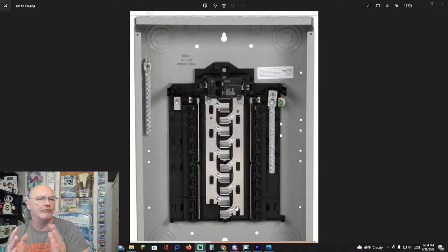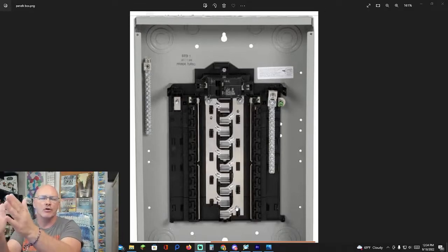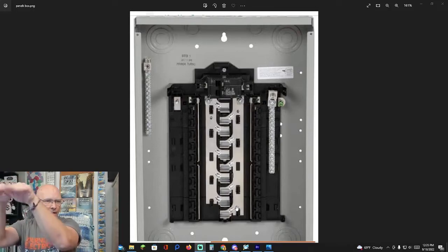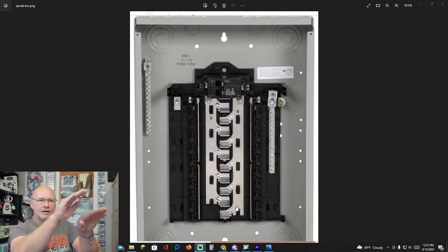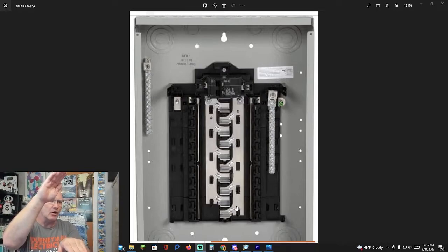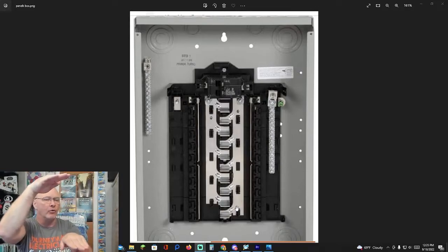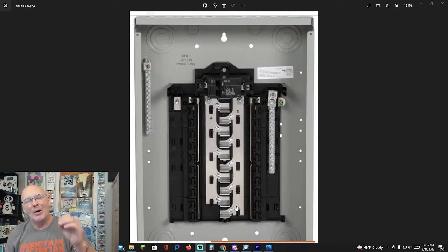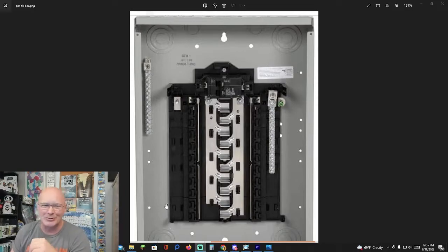So when you're talking about phase voltage, you're talking about the voltage variation across these two. Now, if they were on the exact same phase or wavelength, then when you measured across the two bars on a meter, that would give you a zero voltage because there's no variation in the voltage. They're both up and down at exactly the same time, right? But since one is up and one is down, there's always a variation between the two. And so that's where you get 120 top, 120 down, which gives you a total of 240 combined phase variation. Okay? I know that's really confusing, but I'll explain it more in the breakers. So let's go look at those real quick.